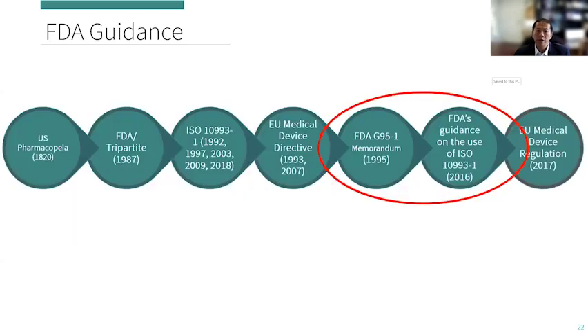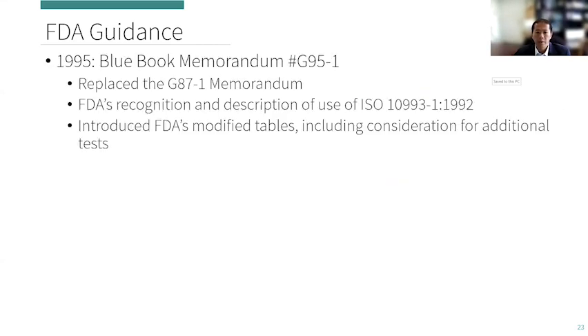And then over time, the FDA also evolved and ended up developing their own guidance, which replaced the 1987 FDA tripartite biocompatibility guidance. So what is the FDA guidance? Well, in 1995, they ended up replacing the tripartite G87 memo with what's called the G95 Blue Book Memorandum.